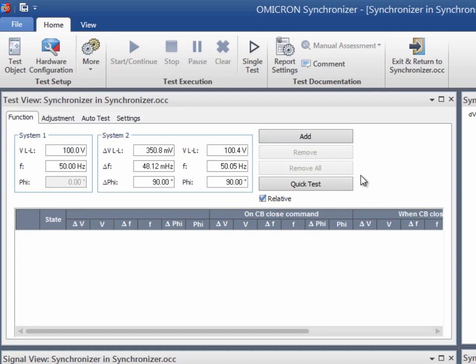The function tab checks the correct performance of the circuit breaker close command under different operating conditions. Based on the synchronization conditions defined in the test object, the module compares the nominal response that is expected with the actual behavior of the relay. As a result of this comparison, the test point is assessed as passed or failed. Remember to check the local hardware configuration before configuring the test module.